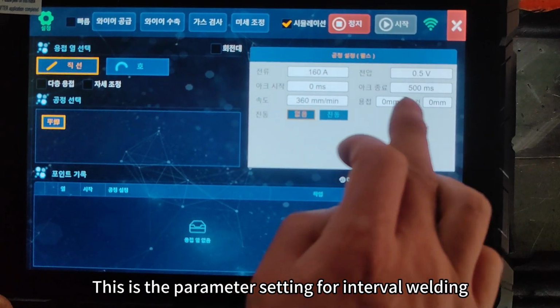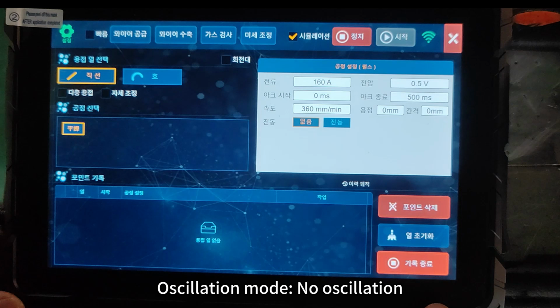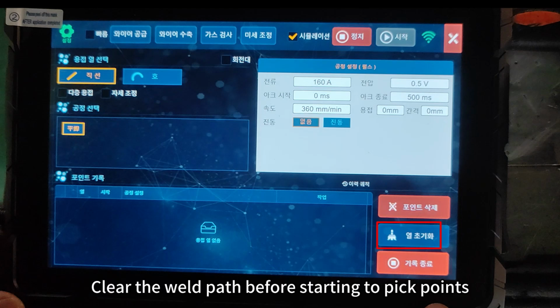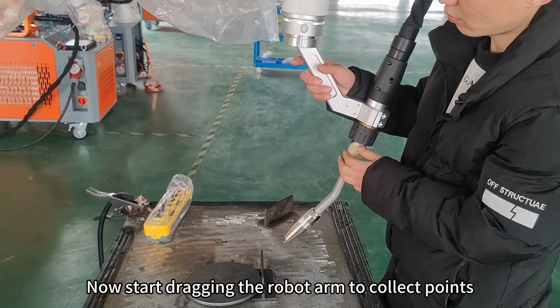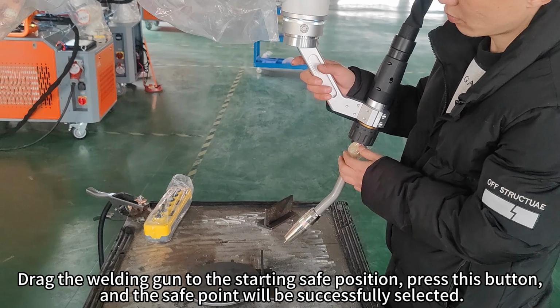This is the parameter setting for interval welding. Oscillation mode. No oscillation. Clear the weld path before starting to pick points. Now start dragging the robot arm to collect points. Drag the welding gun to the starting safe position. Press this button, and the safe point will be successfully selected.